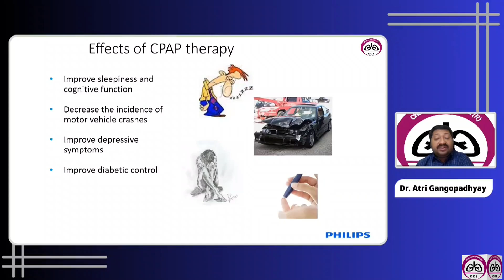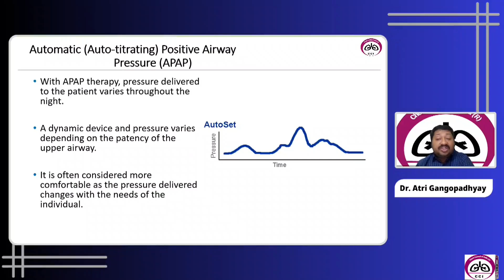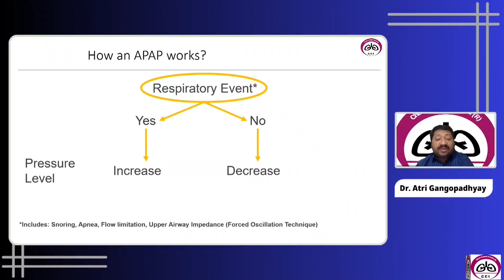Next we come to the APAP, or automatic positive airway pressure. It is a dynamic device, and the pressure varies depending on the patency of the upper airway. It is considered more comfortable as the pressure delivered changes with the needs of the individual. So how does it work? If there is a respiratory event like snoring, apnea, flow limitation, or upper airway impedance, then the pressure level increases, and if there is no such respiratory event, then the pressure level decreases.